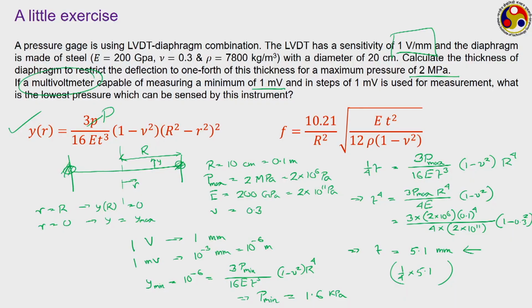Sometimes we are also interested to know the frequency of the oscillation that the diaphragm is going to have, or I should say the natural frequency of the diaphragm, particularly if we are looking for some kind of dynamic measurement. This is not a part of this problem, but the natural frequency of this kind of diaphragm can also be given like this, where capital R, E, nu, T all refer to the values that we have already used. Here rho refers to the density, which is 7800 kg per meter cube for steel in this particular problem. So, you can just put the numbers in this. For this problem, the natural frequency comes to approximately 7979 Hertz. This will be the natural frequency for this particular diaphragm.